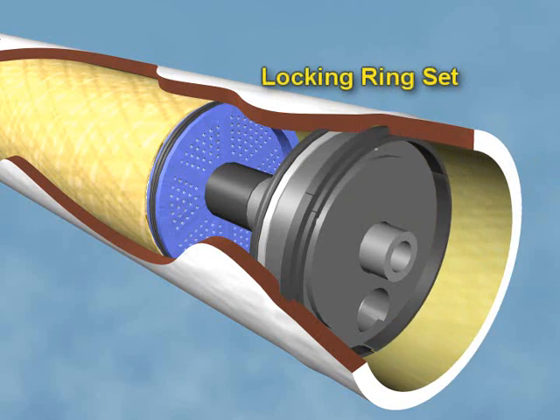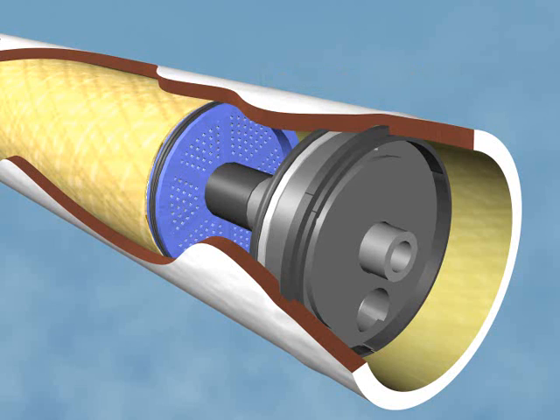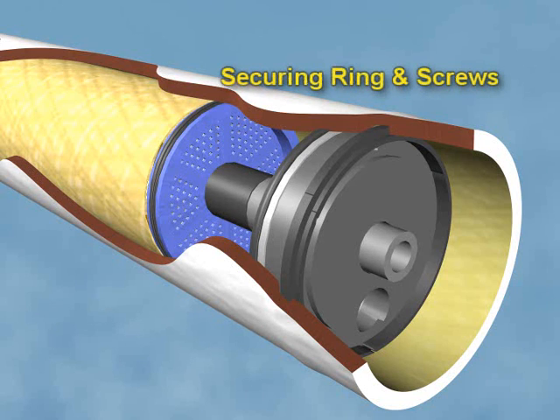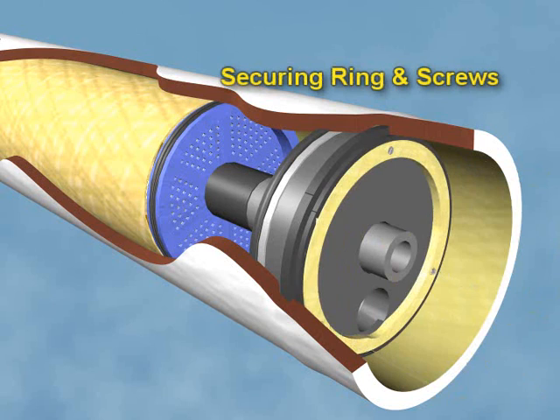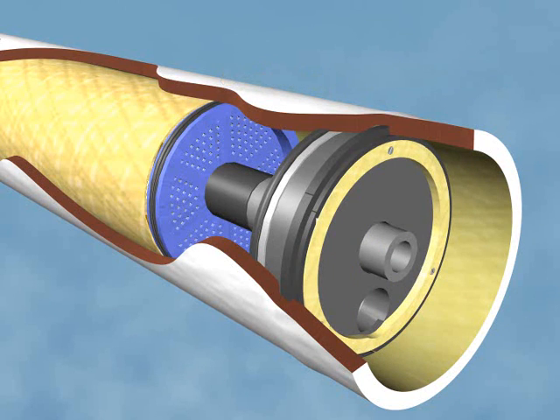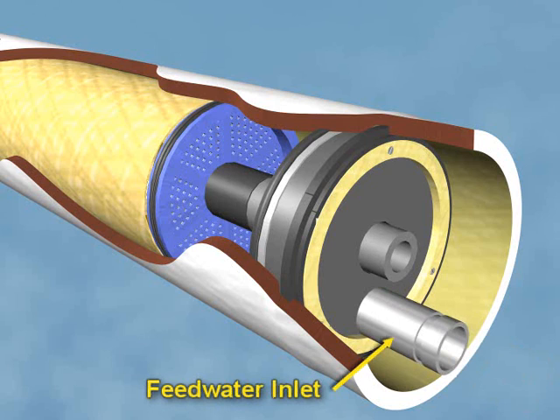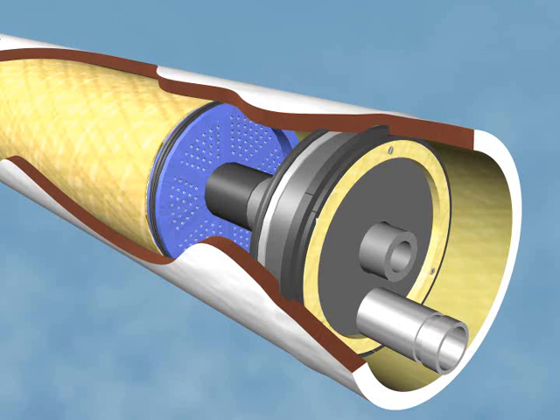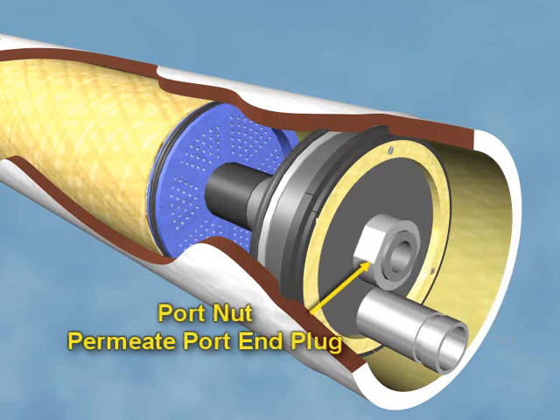A locking ring set that fits into a slot on the inside of the pressure vessel is used to hold these plates in place. A securing ring and screws are used to hold the locking ring set in place. The feed water port fits through the sealing plate to reach the cavity between the sealing plate and the first element. A port nut and permeate port end plug complete the inlet side assembly.